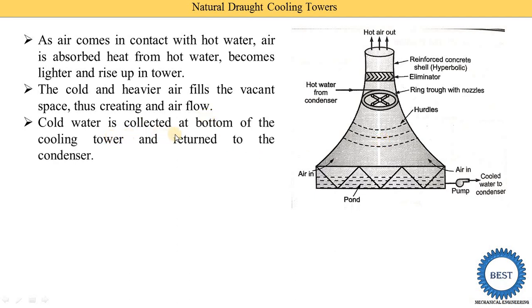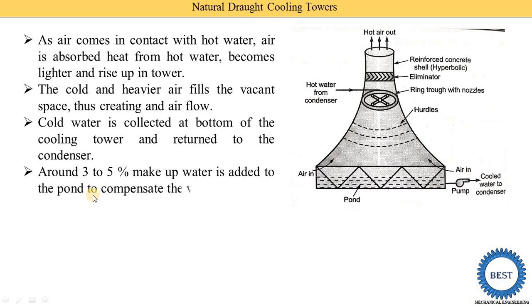Cold water is collected at the bottom of the cooling tower — also called the pond — and returned to the condenser using a pump. Around three to five percent makeup water is added to the pond to compensate for water loss due to evaporation, since some quantity of water evaporates with the air.